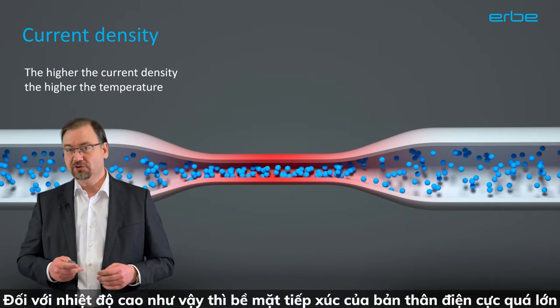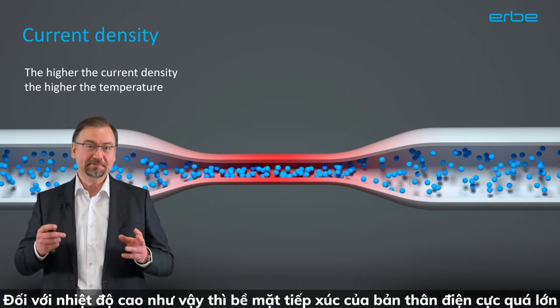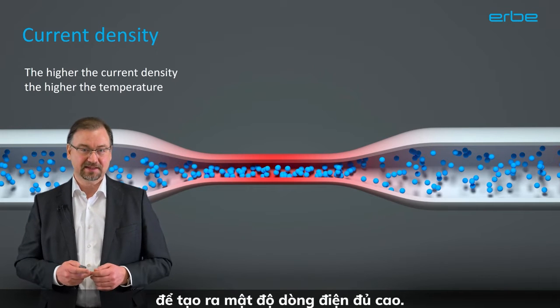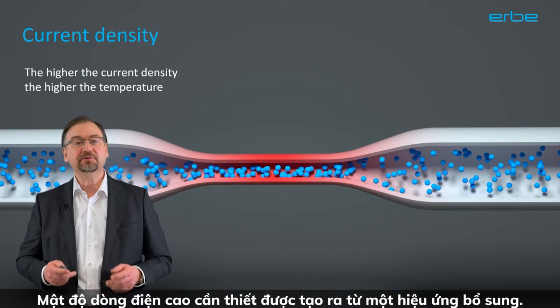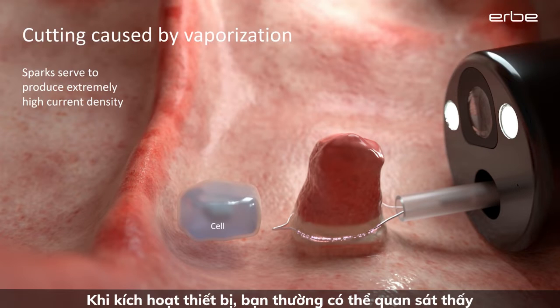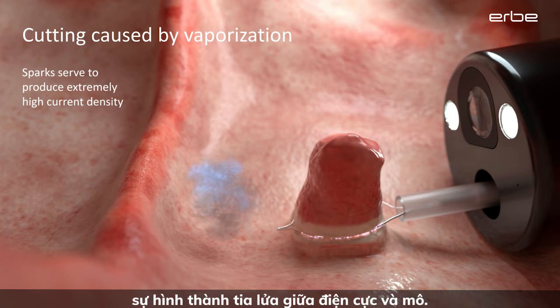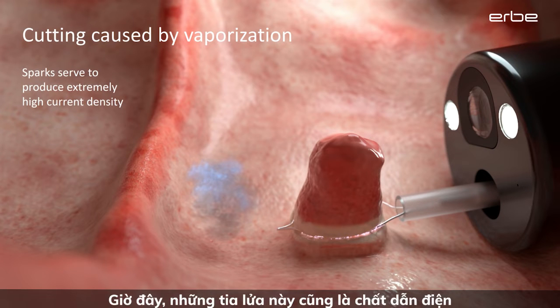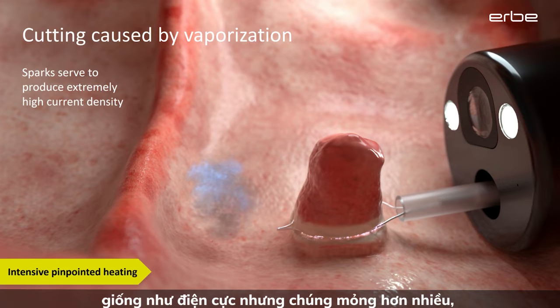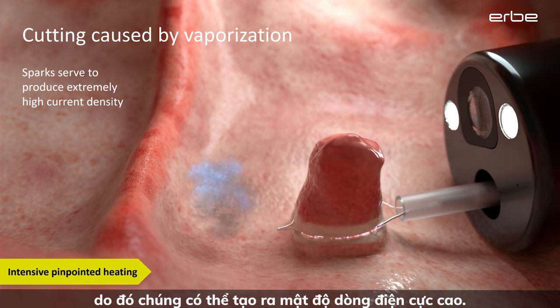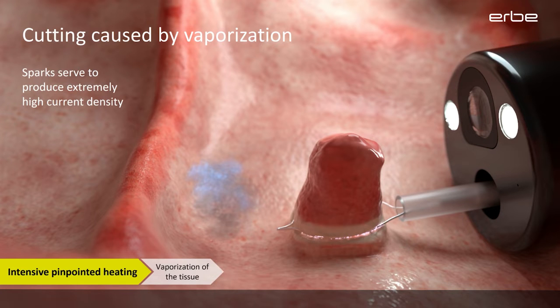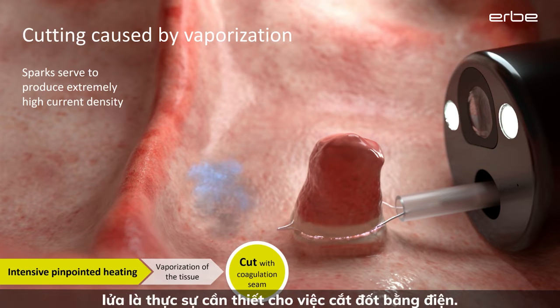For such high temperatures, the contact surface of the electrode itself is by far too big to create sufficiently high current density. The required high current density comes from an additional effect. When you activate the instrument, you can often observe a spark formation between the electrode and the tissue. Now, these sparks are also electrical conductors, like the electrode, but they are much thinner. Therefore, they can develop an extremely high current density. This is how the temperature can become hot enough to vaporize the tissue at the point of contact. This explains why spark formation is essential and actually required for electrosurgical cutting.